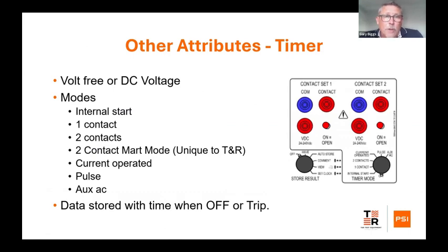The other attribute we have on our unit is the timer. The timer can be either wet or volt free. We have various modes on the timer to allow us to test the different types of relay that we're going to encounter. The first and most common way you'd have the timer set is on internal start.